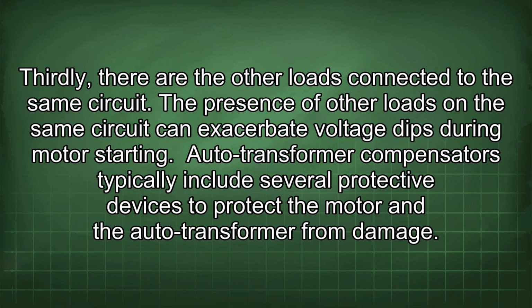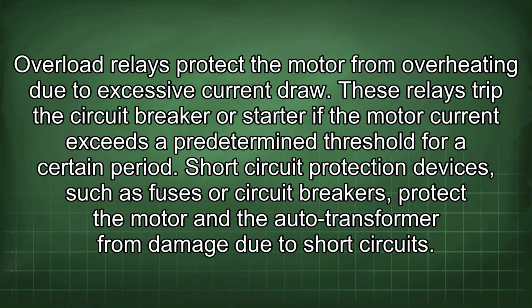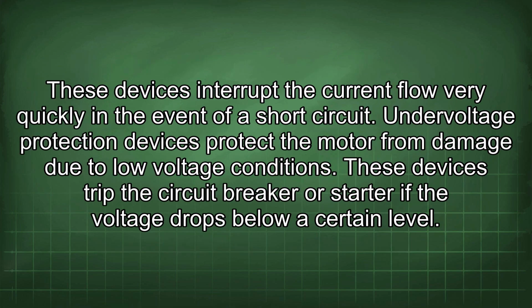Auto transformer compensators typically include several protective devices to protect the motor and the auto transformer from damage. Overload relays protect the motor from overheating due to excessive current draw. These relays trip the circuit breaker or starter if the motor current exceeds a predetermined threshold for a certain period. Short circuit protection devices, such as fuses or circuit breakers, protect the motor and the auto transformer from damage due to short circuits. These devices interrupt the current flow very quickly in the event of a short circuit.